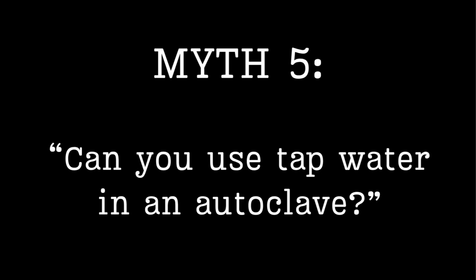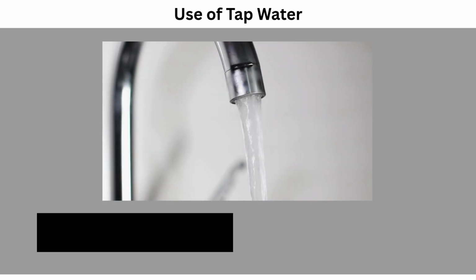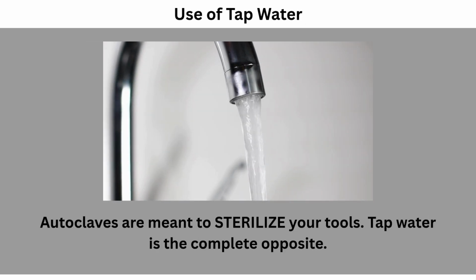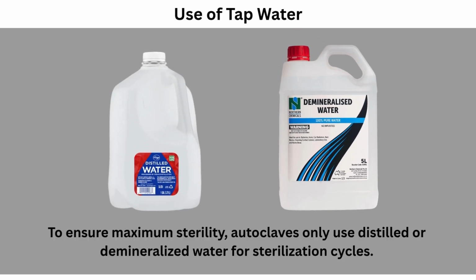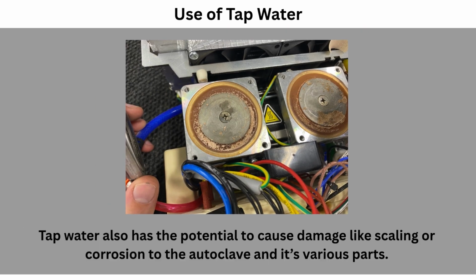Myth number 5. Can you use tap water in an autoclave? Autoclaves are meant to sterilize your tools. Tap water is the complete opposite. To ensure maximum sterility, autoclaves only use distilled or demineralized water for sterilization cycles. Tap water also has the potential to cause damage like scaling or corrosion in the autoclave and its various parts.